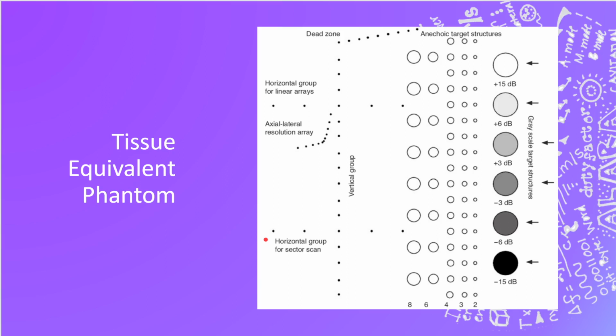Another interesting spot is this set of curved pins. When we scan from the top, we can check the axial resolution. What we are looking for is, can we see all of these pins displayed in the vertical plane? Remember, as the pins get closer, they start to be displayed as one if the frequency or the wavelength is too long to display both.